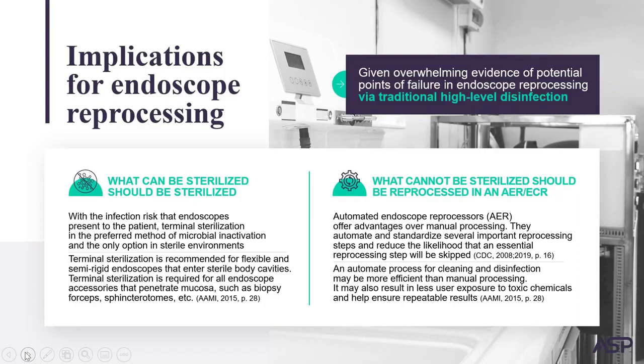This aligns with FDA recommendations that users should be instructed to thoroughly clean semi-critical devices and then reprocess them by sterilization. If the device design does not permit sterilization, for example, the device materials cannot withstand sterilization, then high-level disinfection should be used.